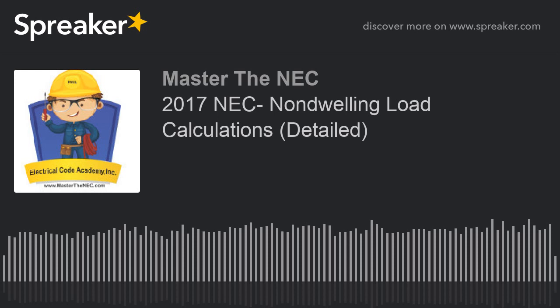So any continuous loads that operate 3 hours or more, I'm going to take this at 125%, whatever that load may be. Okay, if it's 15 amps and that 15 amps load is done as a continuous load, then it's 15 times 125%. The load doesn't change; it's still 15 amps. But for use in the calculation, we have to take a load at 125%, even though that additional 25% is kind of invisible. It's just a fudge factor built in because the code says we have to adjust for that as a continuous load. Then that's what we're doing.